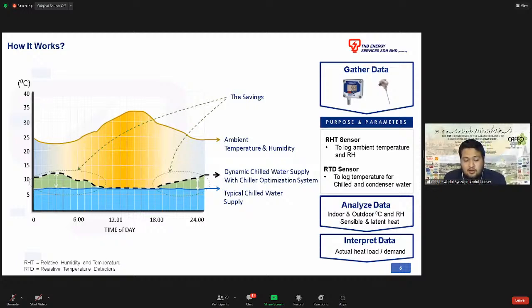Let's say in our office, at that particular time of day, we need the system to regulate the chilled water temperature to cater exactly to the demand for that time of day. Using this system, the chilled water supply temperature will float accordingly.